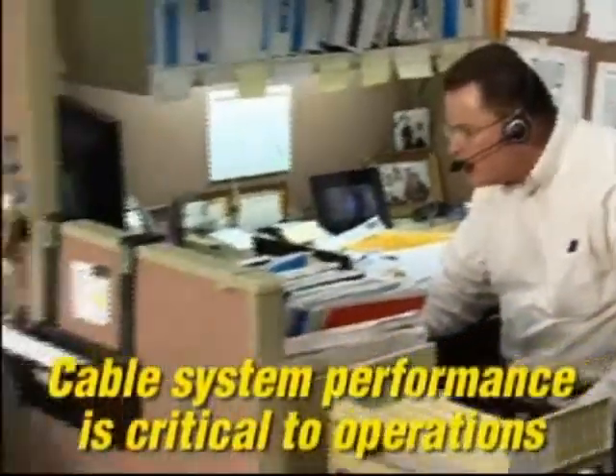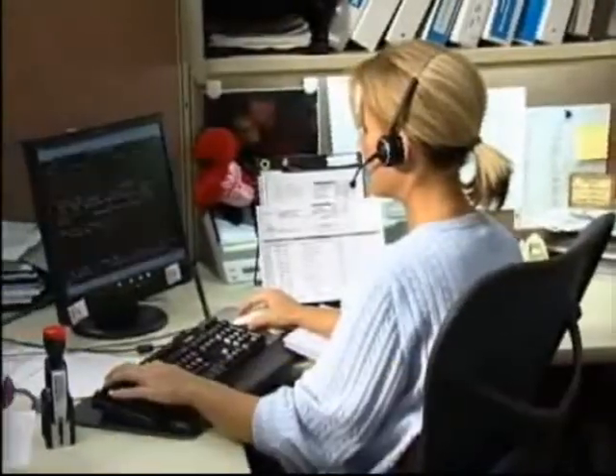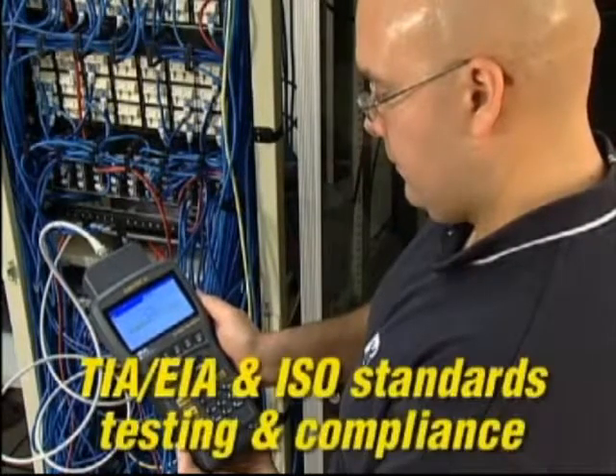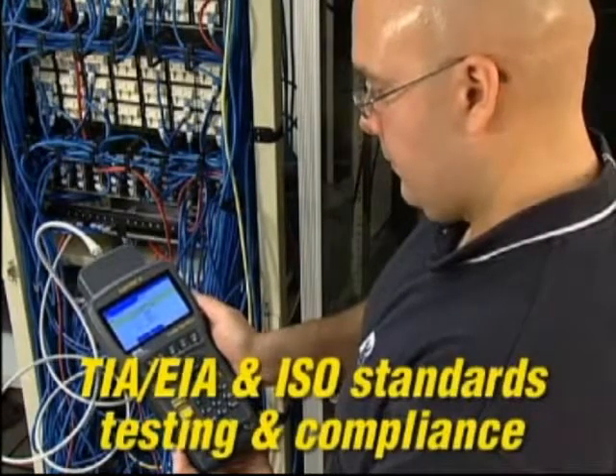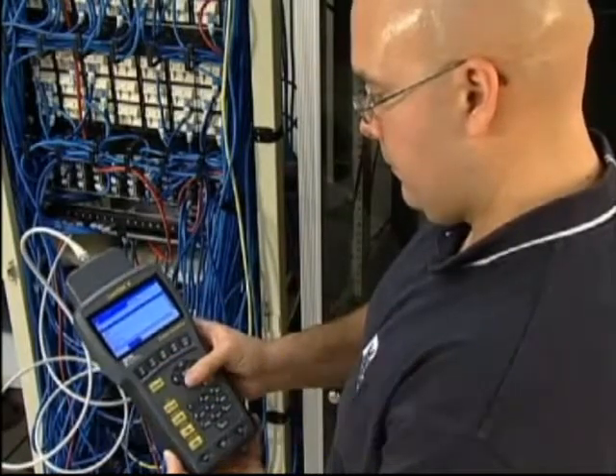The quality of a cable system installation is critical in schools, hospitals, industry and businesses. Categories or classes are used to designate the differences in unshielded twisted pair, screen twisted pair, and shielded twisted pair cables. The most common designation is the maximum frequency it will support per pair. Cable certifiers like the LanTEK II perform the tests required by TIA, EIA and ISO standards to certify these cable categories.